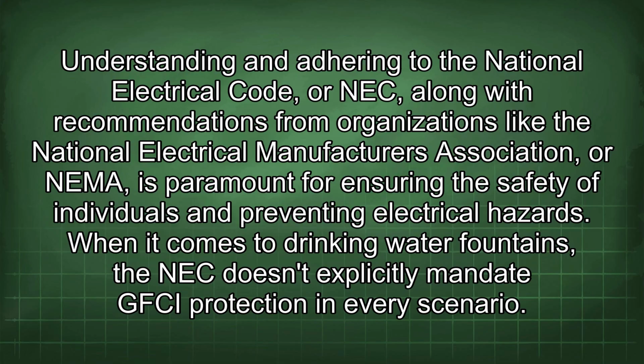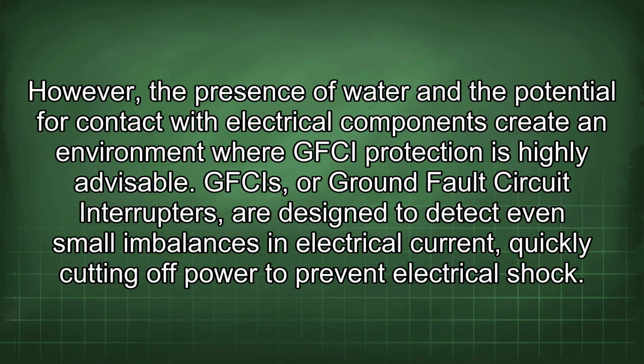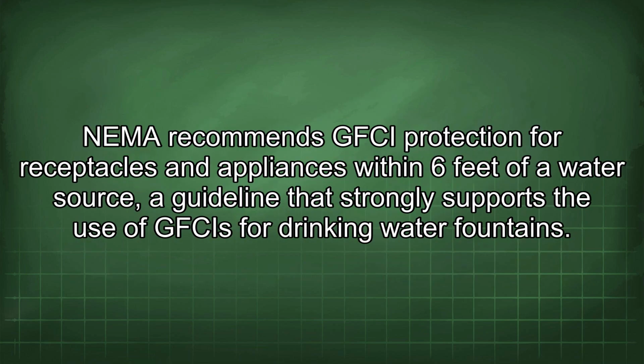When it comes to drinking water fountains, the NEC doesn't explicitly mandate GFCI protection in every scenario. However, the presence of water and the potential for contact with electrical components create an environment where GFCI protection is highly advisable. GFCIs, or ground fault circuit interrupters, are designed to detect even small imbalances in electrical current, quickly cutting off power to prevent electrical shock. NEMA recommends GFCI protection for receptacles and appliances within 6 feet of a water source, a guideline that strongly supports the use of GFCIs for drinking water fountains.